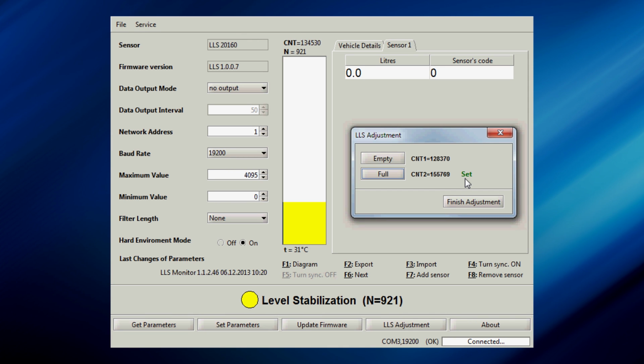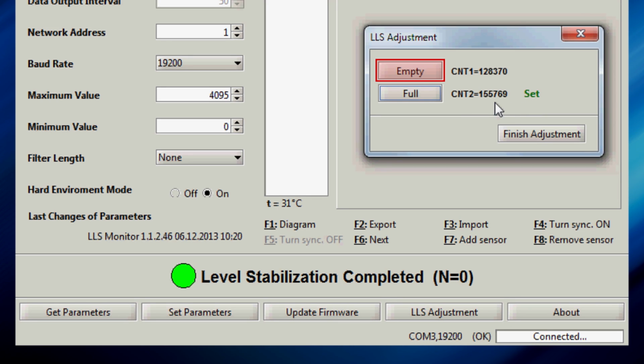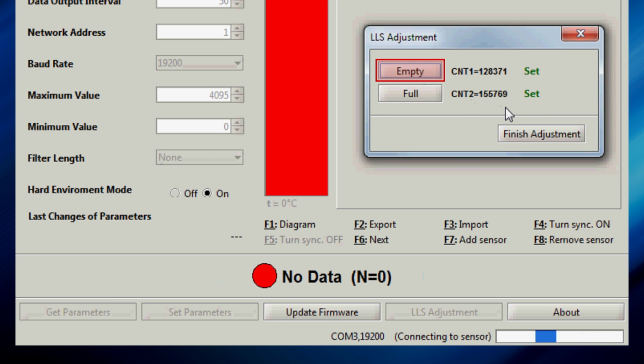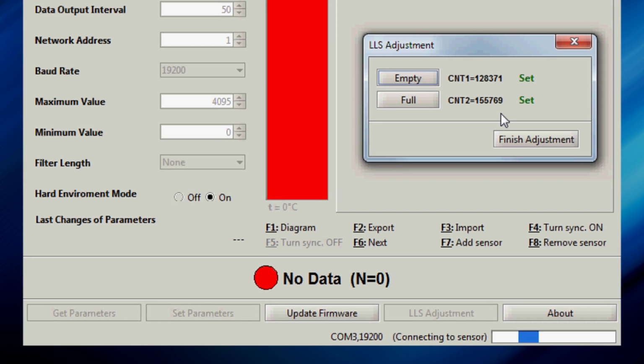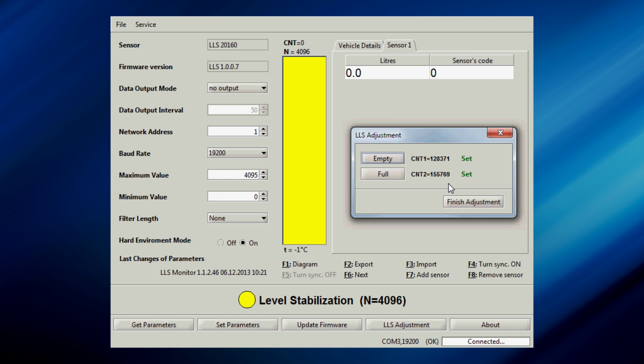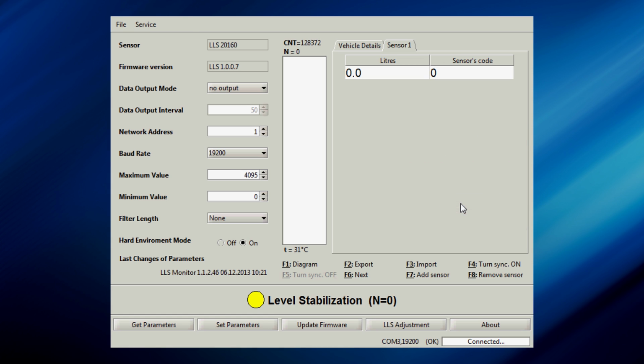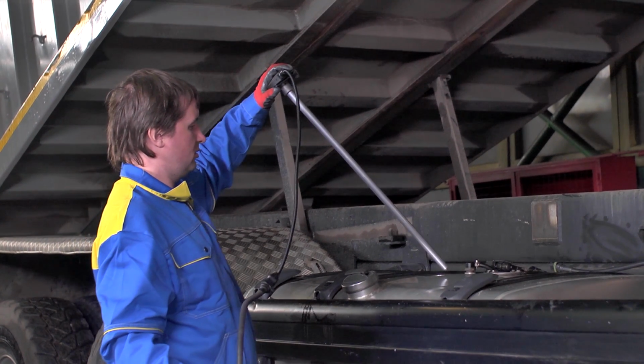Wait for the fuel level to stabilize in the LLS monitor application, and then click the empty button in the sensor configuration section of the application. The new setting will be saved in the sensor memory, at which point the configuration of the full versus empty parameters is completed. The sensor is ready to be installed.